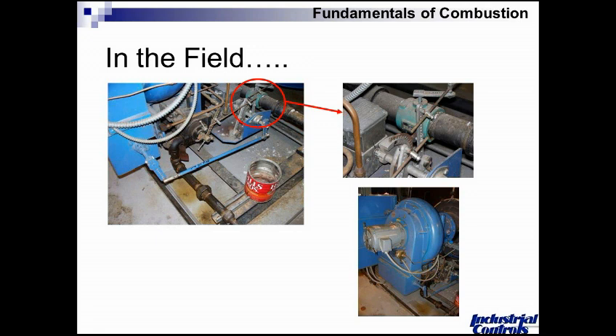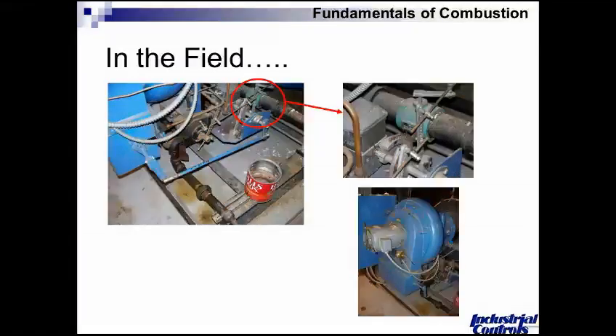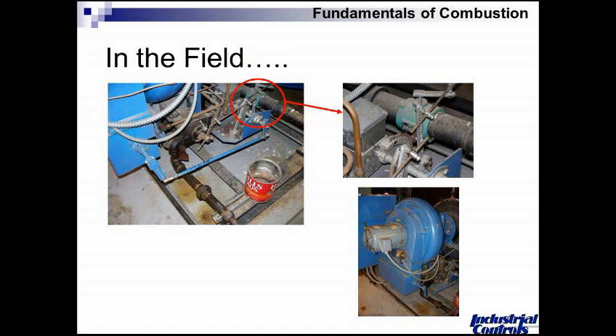Likewise, as you might expect from a butterfly valve, which is a round disc in a round pipe, as you change the position of that butterfly valve, you do not see incremental changes in volume with incremental changes in stem position.